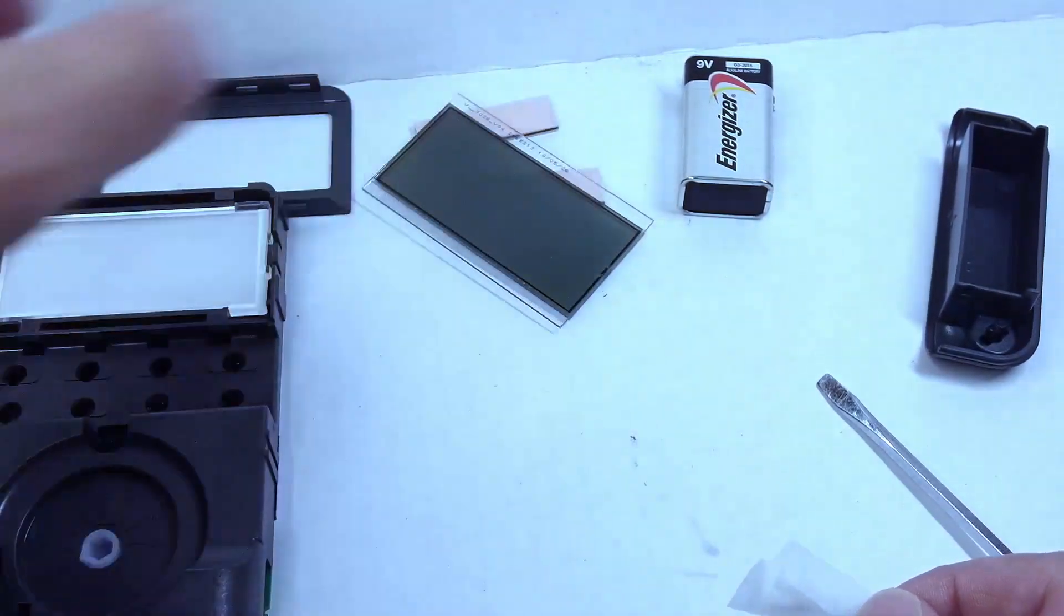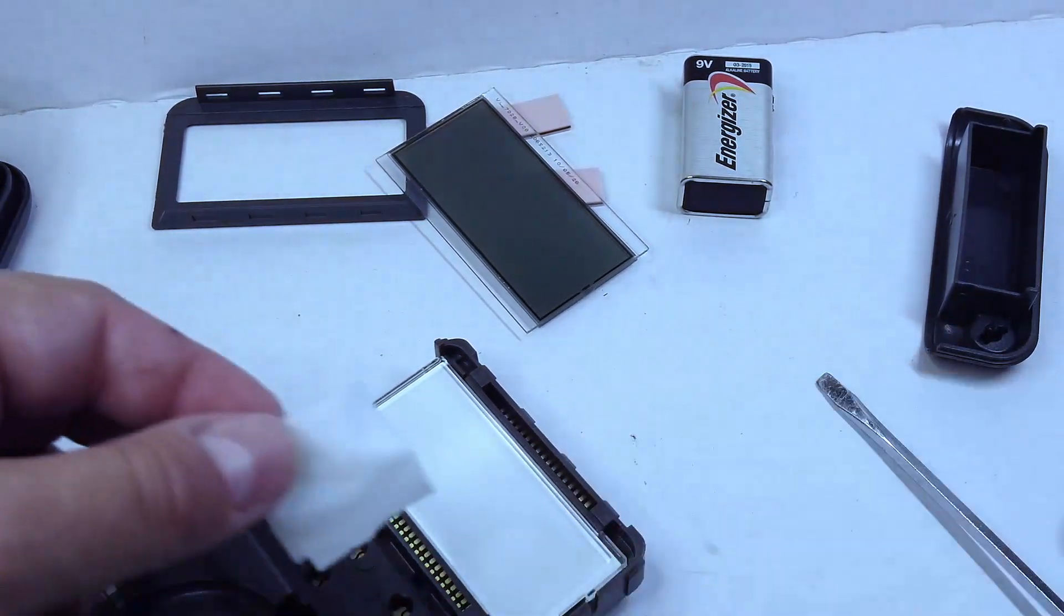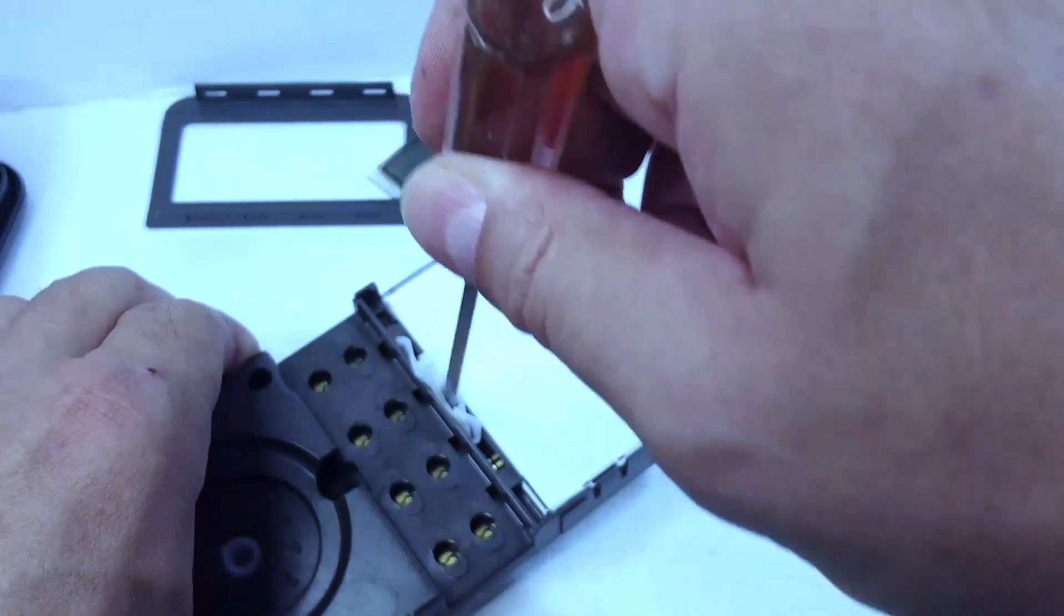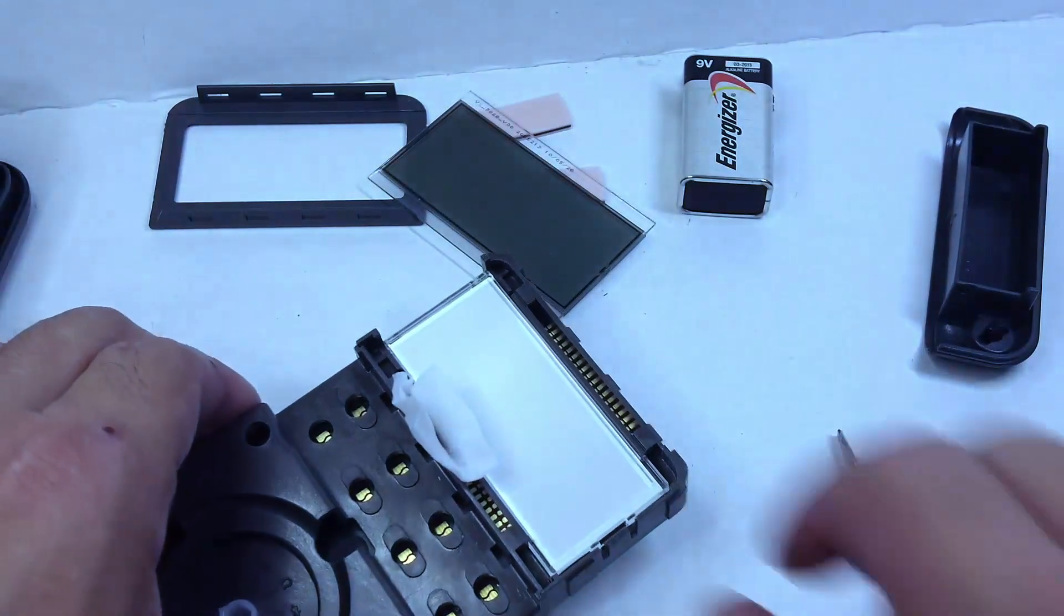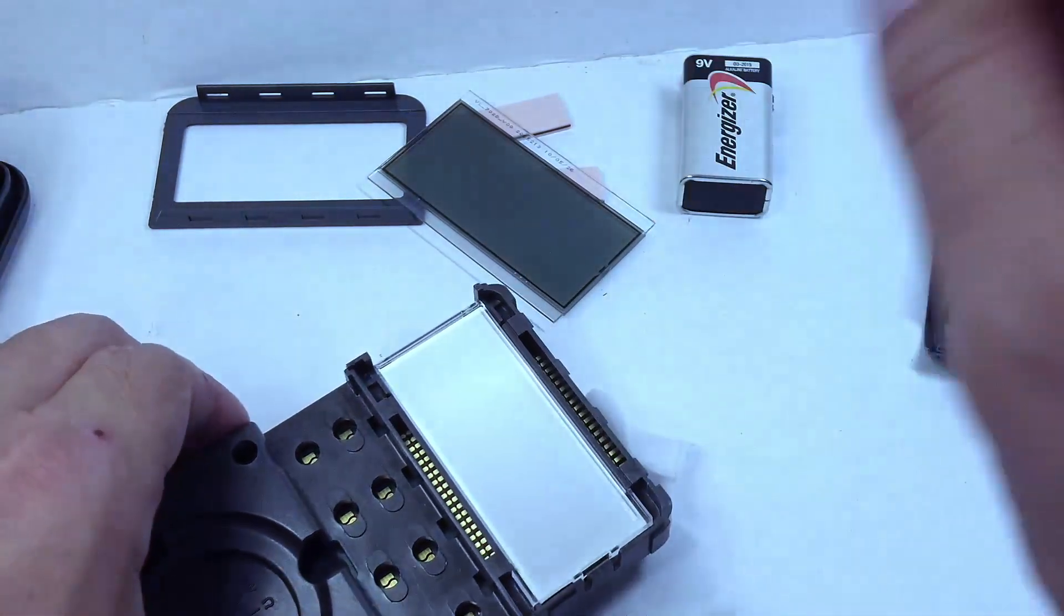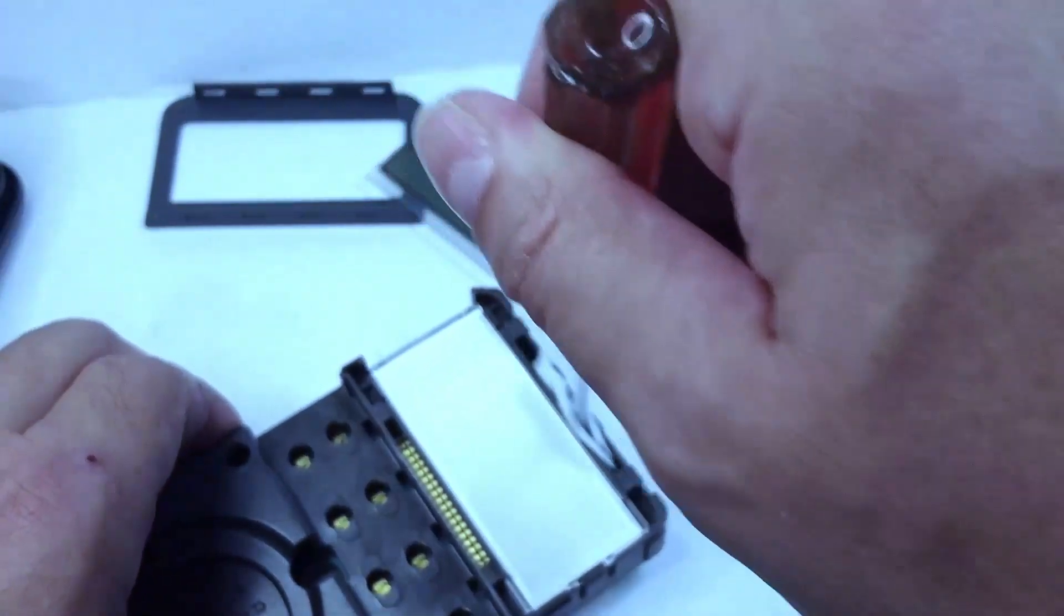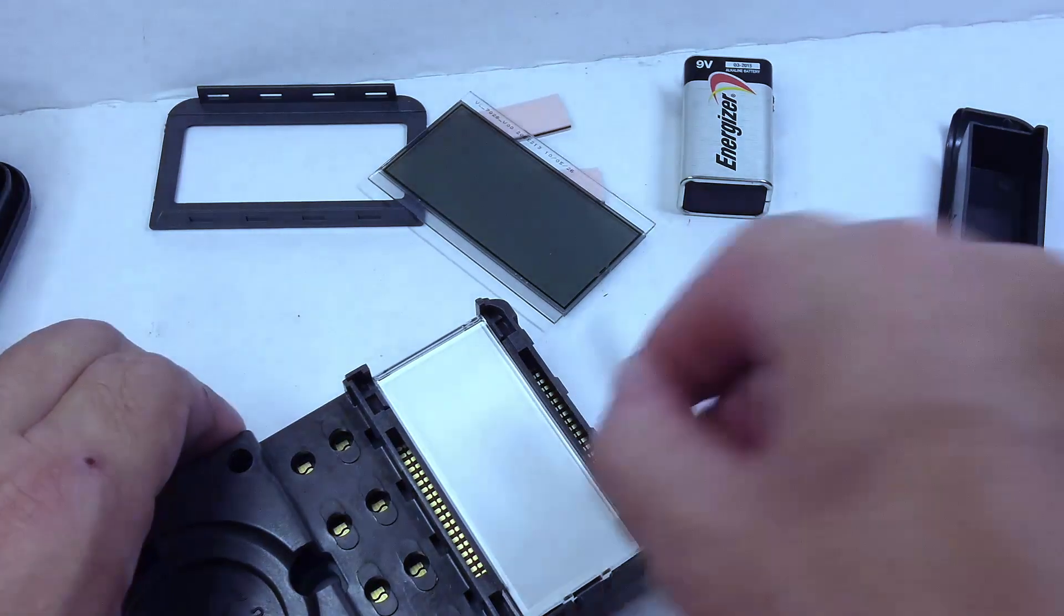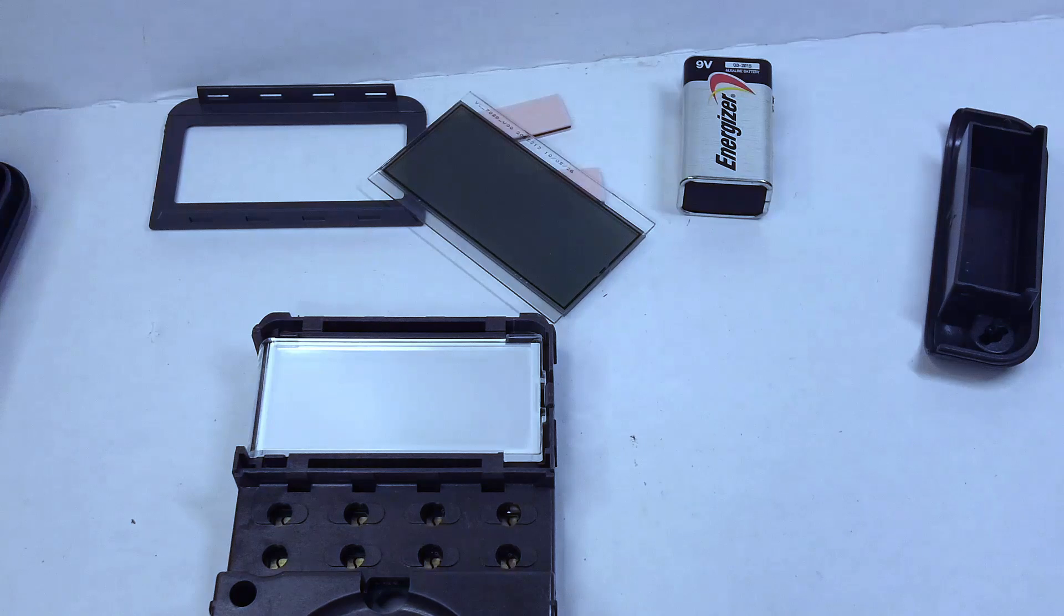And I'm going to set this aside so now I can get inside here to these slots and clean these as well. I'm using the same alcohol pad, and I'm just wedging it in there and just sliding it back and forth. If these are real dirty or dusty, if it's an older unit that's had some penetration because the dust seal was missing, I would probably use a different alcohol pad to clean this part. But this one's nice and clean, so I think it's okay to use the same pad.